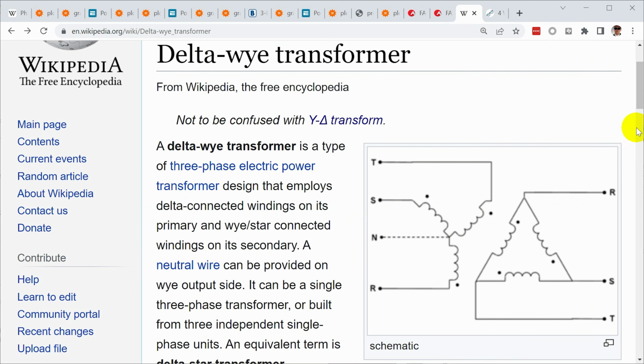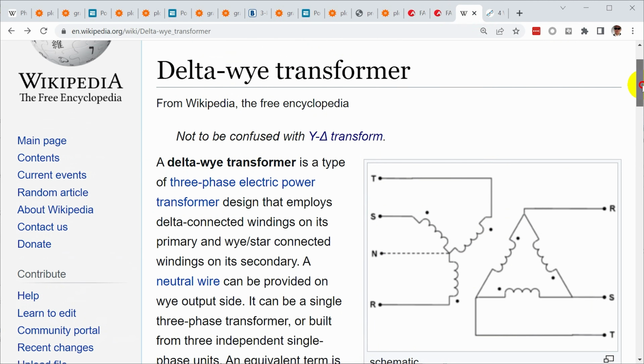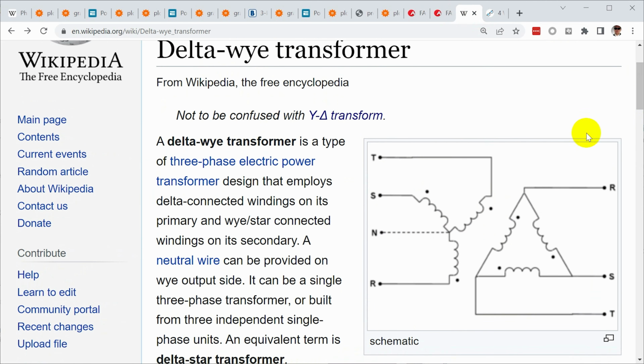Well, if you pop out to Wikipedia, they actually have some information about delta Y transformers and how they work. And essentially you have two sets of coils, one configured as delta, one configured as Y. So you can take the output of your rotary phase converter, feed it into the delta windings. This is magnetically coupled across, and it energizes these other coils that are in the Y configuration with a center point reference. You take that center point reference and you attach that to ground, and presto, you have a neutral ground referenced Y configuration power source.